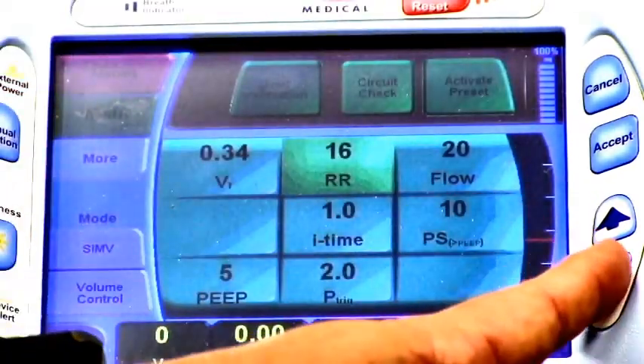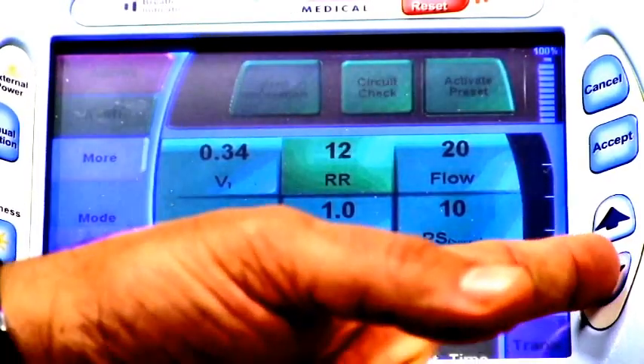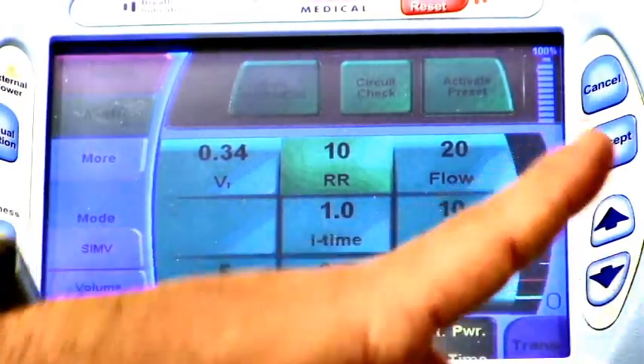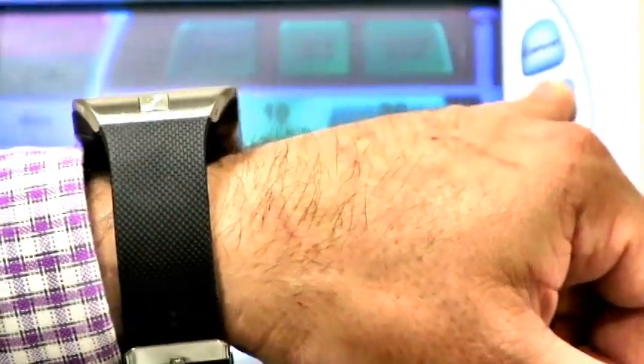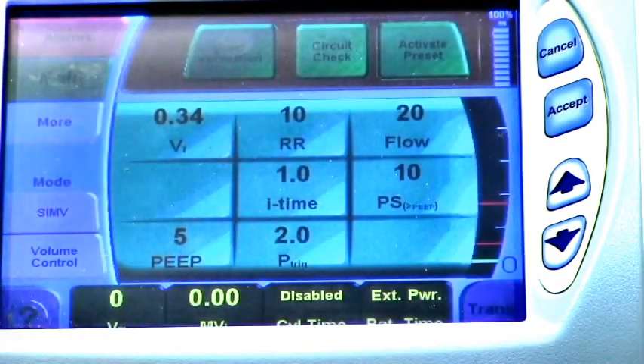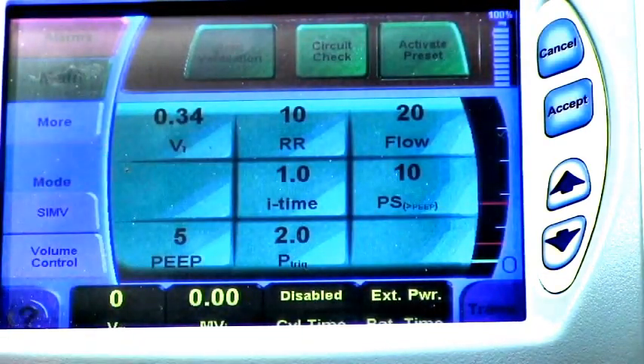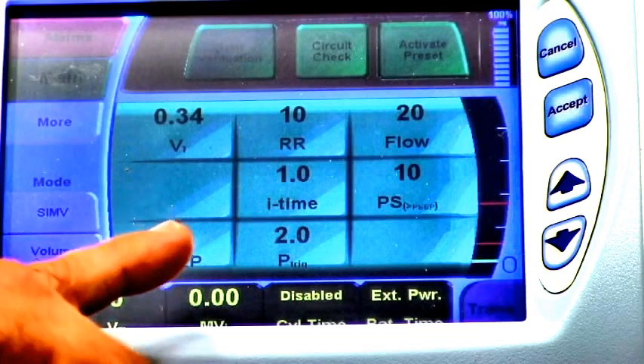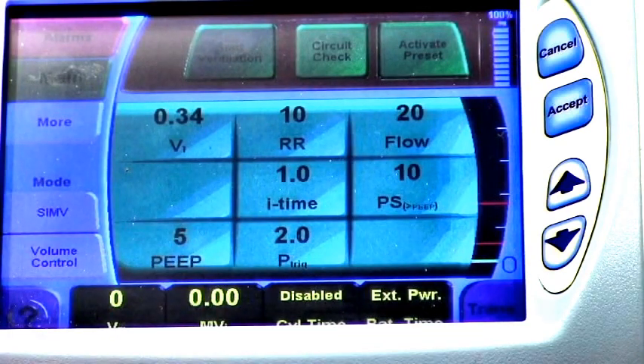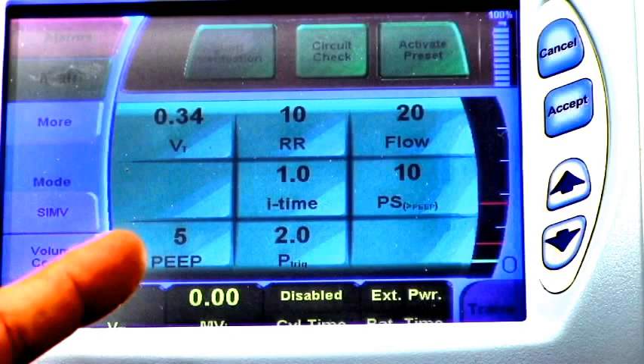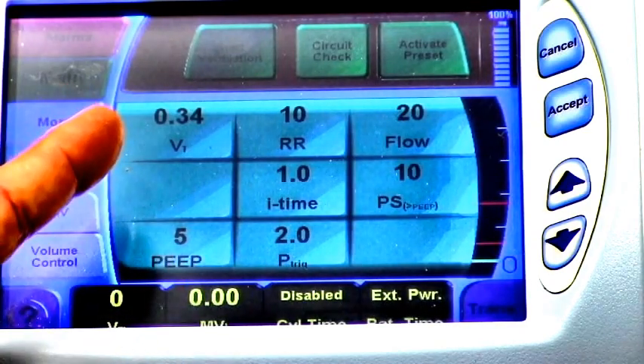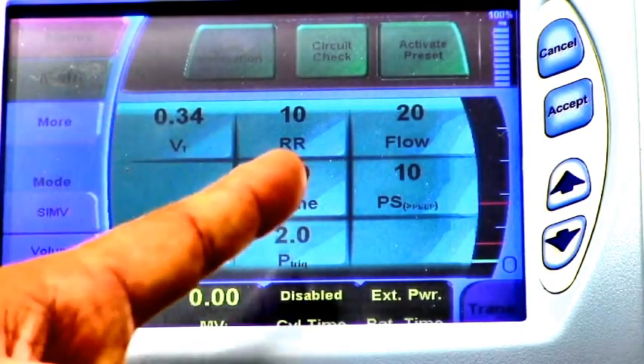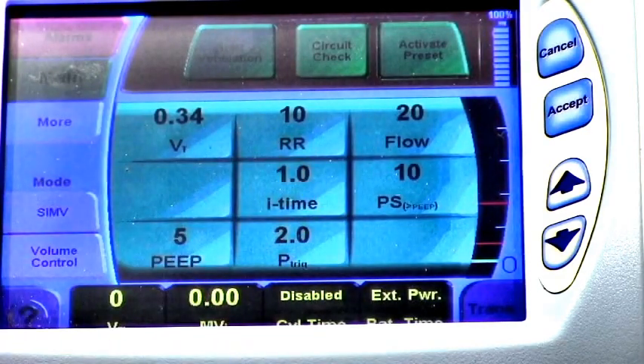For this patient, we're just going to set a respiratory rate of 10, just so as I'm talking here, it's not so loud and interrupting as we go through. Again, it's dark green as I change it. When I'm done, I want to hit accept. When I hit accept, that will default back to that green. Your flow, I want you to ignore that that's even there. What we change is going to adjust the flow as needed, and it's not something that we really need to mess with. Your I time is inspiratory time, so that's the amount of time that this machine is going to deliver the full 340 cc's of air. Right now it's set at I time of 1, so the I time is over 1 second.